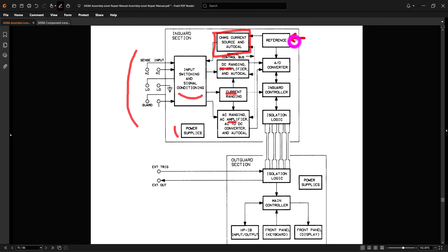So you can see the reference feeds obviously the data converter, as well as everything that goes into all of these internal auto calibration measurements, because they all have to be based on essentially the same reference, aside from having precision resistors and so on built in. The logic circuitry and so on over here obviously is working because the instrument is powering on. It does, however, have somewhere on here the places where the SRAM is storing calibration and user data, and I think that second error that we saw is from this. We'll have to take a look at that later. But we can bring up the schematic of this portion. The schematic of the entire instrument is enormous. There's a lot of stuff there, but we can focus at least on this part.